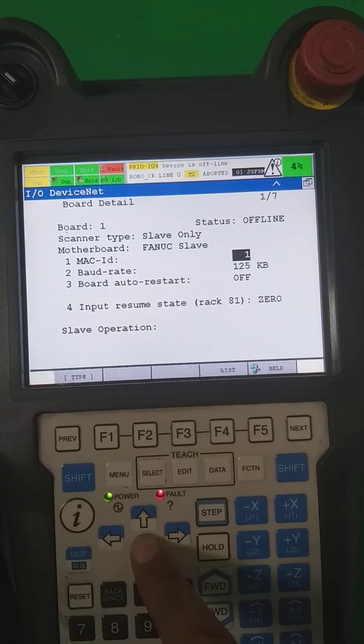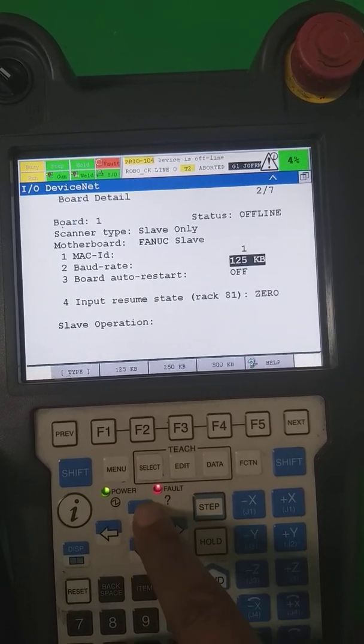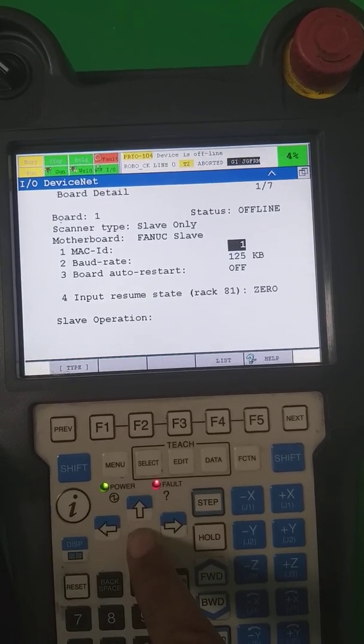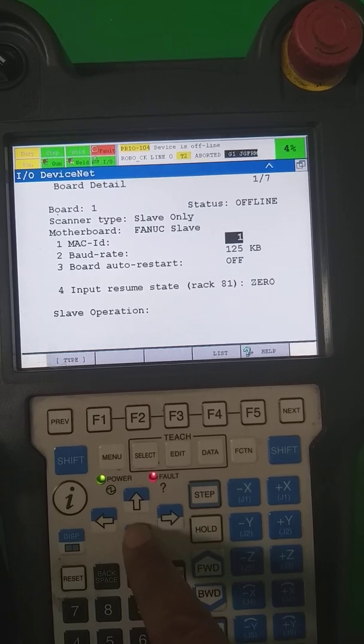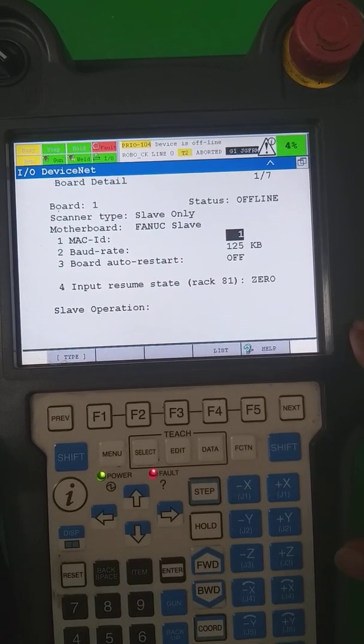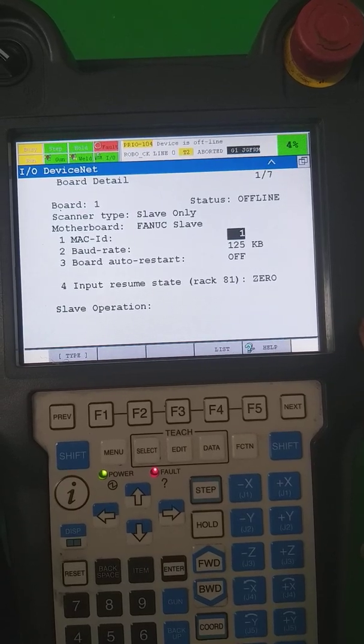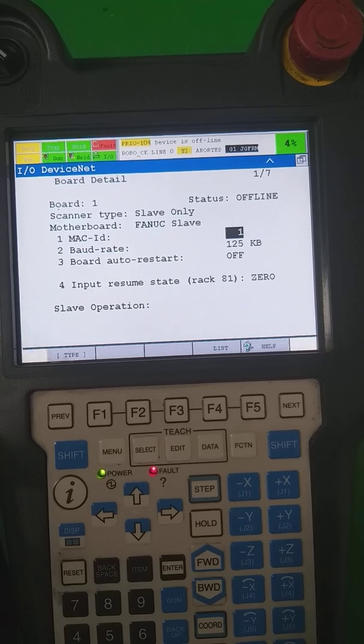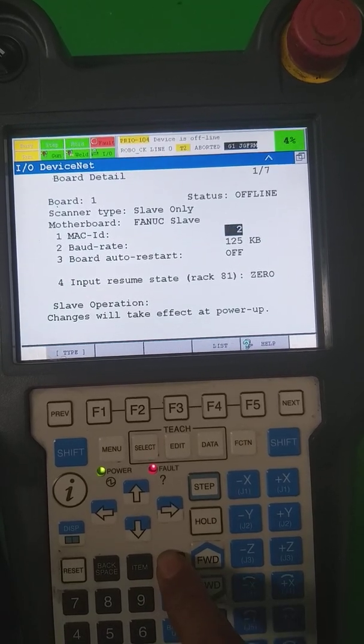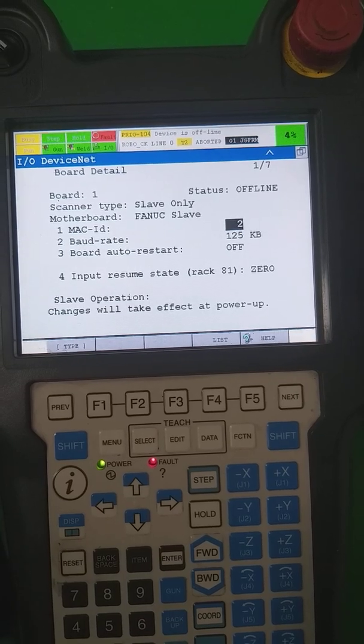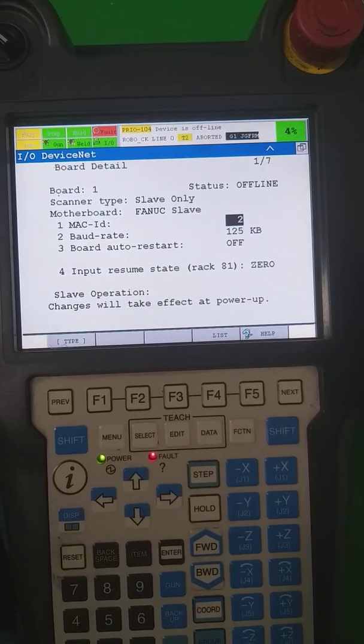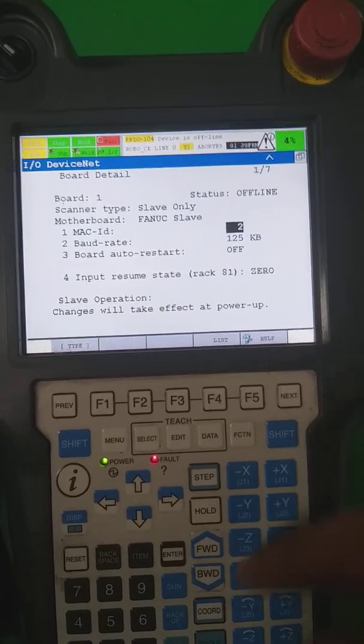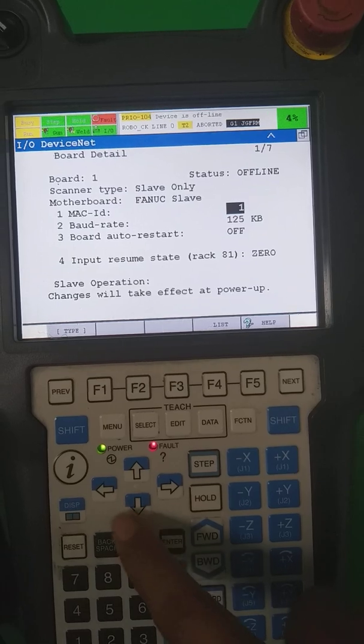From the first one, this is the scanner type slave only, motherboard FANUC slave, and MAC ID. This is the DeviceNet MAC ID, generally this is called the node ID. What a node ID you want to keep for this robot, it's according to your network. We provide this robot number one. It's editable - you can edit. If I want to put the MAC ID number two, that time I have to tell the programmer or have to write in our network that this robot having the MAC ID number two. So I make it again one.